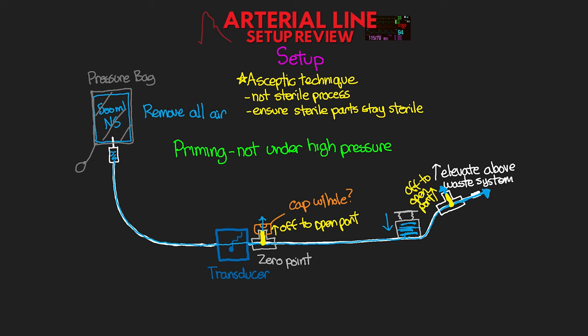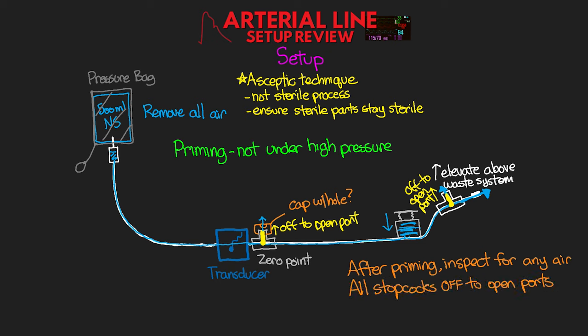Now, once you have everything primed, you want to inspect the entire length of the tubing for any air that may be trapped. It's really important that we ensure that all air is removed from this line. Continue flushing and priming if you do see any air bubbles present. When you do this, make sure that all of the stopcocks are off to the open port, this way to ensure that no air is entering the system here.